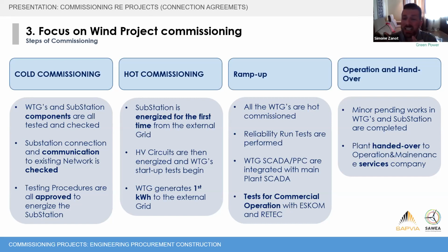Hot commissioning is the stage when the substation is finally energized for the first time from the external grid. We supply power to the power conversion unit, with the inverters and trackers in a solar farm, or the wind turbine generators in a wind farm, via the HV equipment, the HV cables - the so-called collectors - which link the substation to our generating units, either a wind turbine or a power conversion unit.